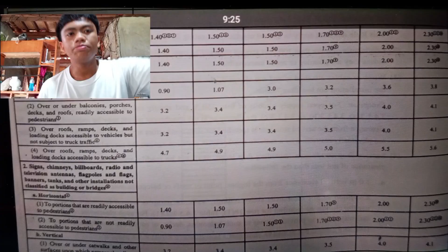Explanation. These are the general clearance requirements. The document specifies minimum vertical clearances for service conductors or cables above roofs, balconies, and other accessible areas to ensure safety and prevent accidental contact. It distinguishes between readily accessible and not readily accessible roofs or balconies, with different clearance requirements applying to each. A roof or balcony is considered readily accessible if it can be reached without extraordinary physical effort or tools.